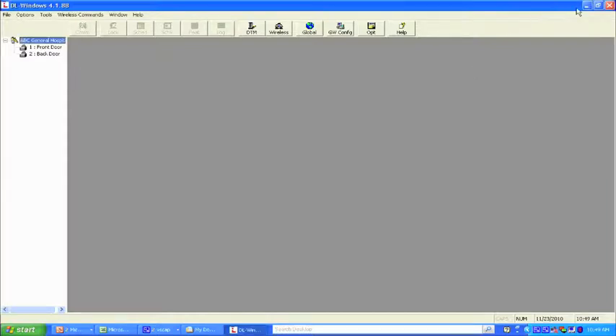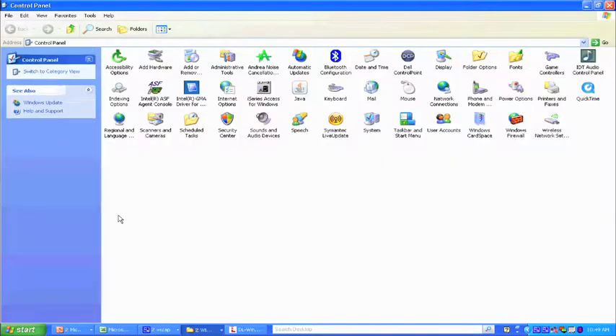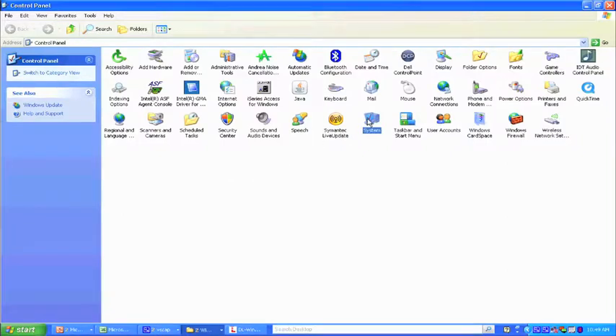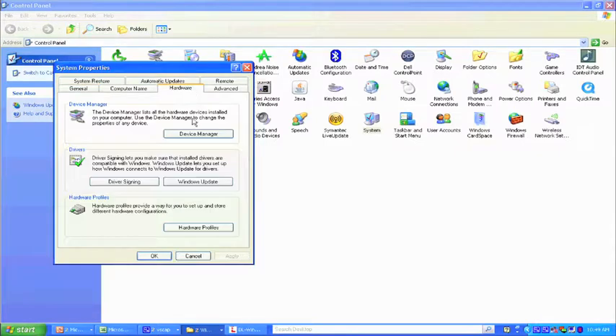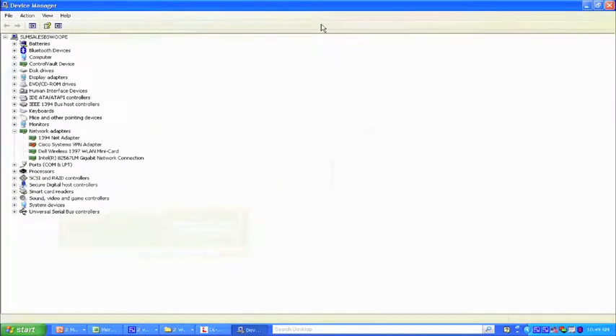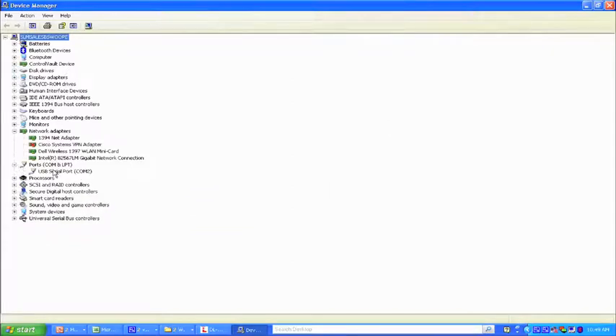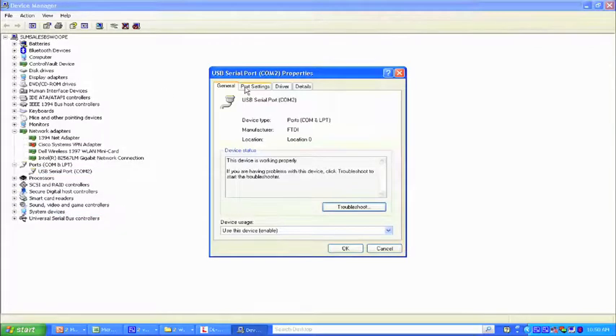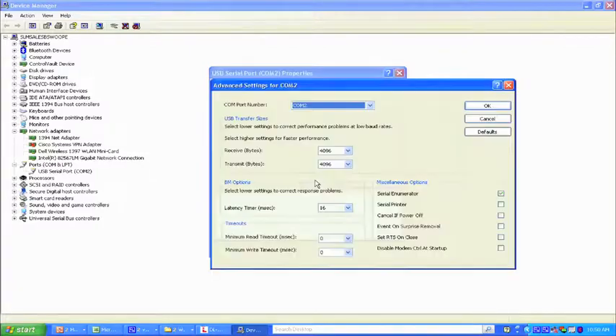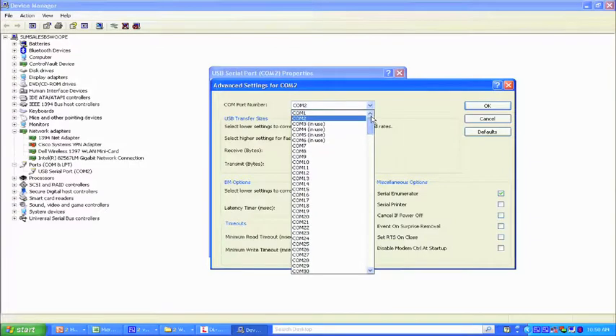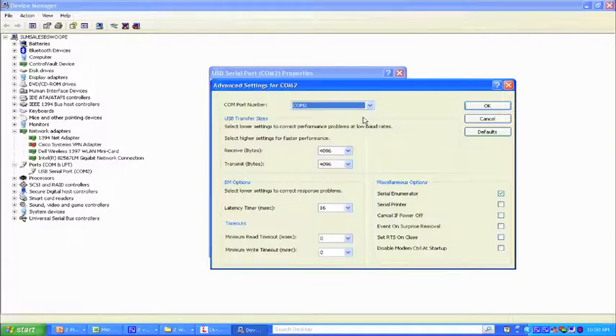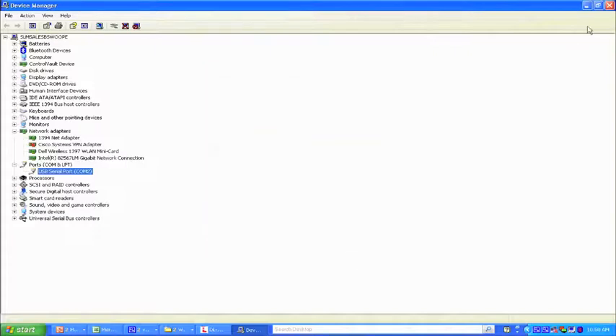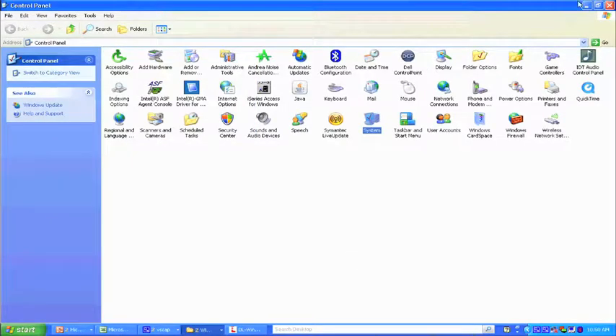If that does not appear and you see 'invalid port' or 'port already open,' minimize the screen and go to the Start button, find the Control Panel, and look for System. Double-click, go to Hardware, then Device Manager. Find the Ports section, right-click, choose Properties, then Port Settings, then Advanced. Look for which COM ports are not currently in use — COM ports 3, 4, 5, and 6 may be in use. We want to use COM port 2. Set it, hit OK, and close out the screens.